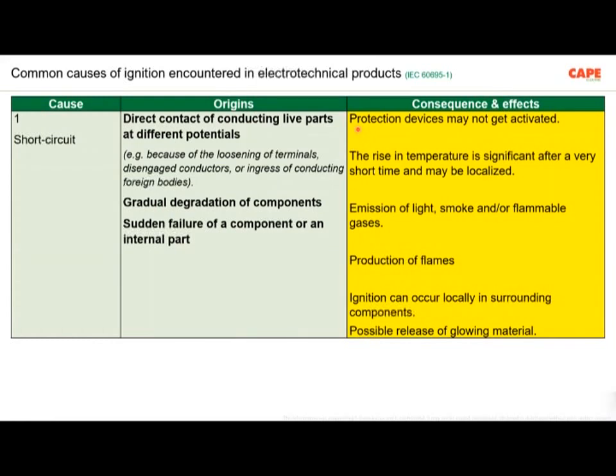The effect number 1, the protection device may not get activated. The most important point is, in case of any abnormality, the protective device is supposed to operate within a certain time. In case of an overload or overcurrent, for example, the wiring and the MCB, the protective device, are selected in such a way that the conventional disconnection time and the conventional disconnection currents are what the whole system is able to withstand. So we explained this the last time, but what I am explaining here is that the protective device must get activated, and if the protective device fails to get activated, we will be in trouble.